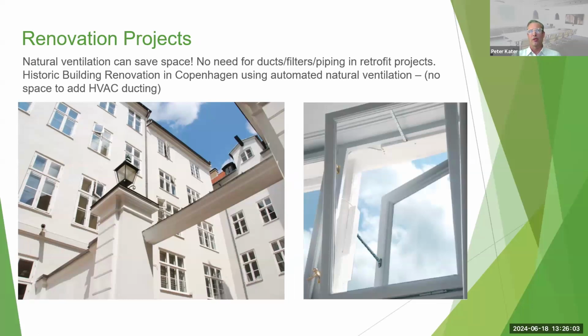This slide talks about renovation projects where you're retrofitting an existing or historic building with a natural ventilation system. So you're putting these actuators on the windows. You can see on the right the actuator operating that hopper window there. The advantage of this over retrofitting the building with a mechanical ventilation system is you don't need space for air ducts within the building because the air is coming in through the operable windows. The only ducting you need really for the natural ventilation system is conduit for the wiring. That can be easily concealed and doesn't take up much space. So it provides benefits for the aesthetics of the renovated building versus trying to mechanically ventilate it.